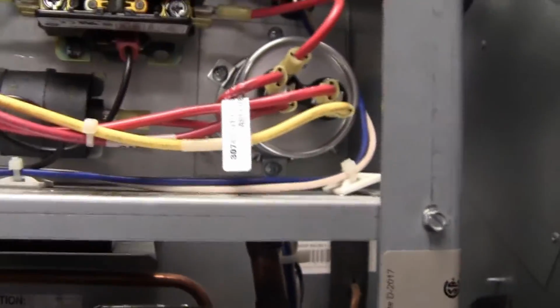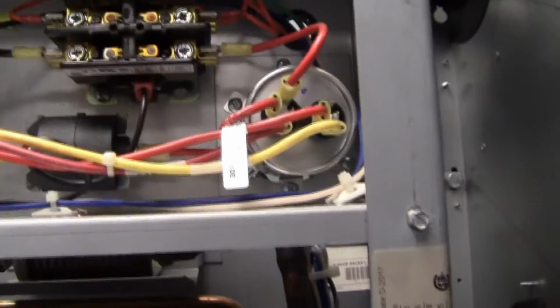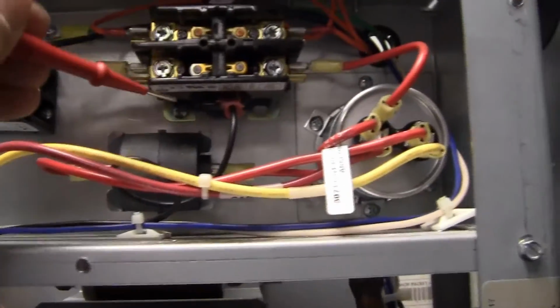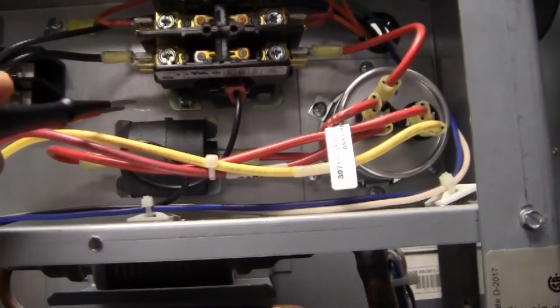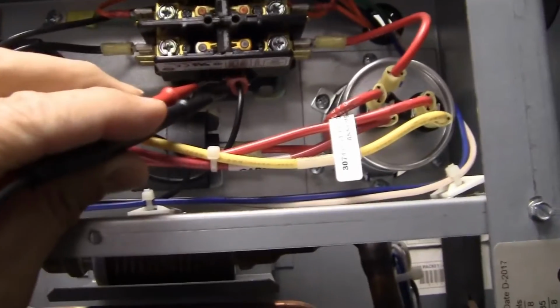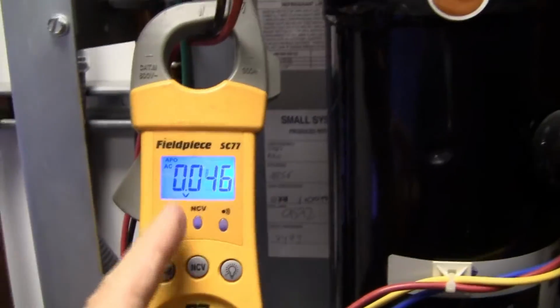So this thing has experienced some pretty good wear and tear. Anyways, I've already checked for voltage across the leads right there at the bottom. Hang on one second. Okay, so it's hard for me to do this and hold the camera at the same time, but basically, without holding the camera in my hand, I checked voltage from this lead to this lead right up here, which is the contactor coil, and it came out with 0 on my Fieldpiece. Now, that means there's no coil voltage, but the compressor is stuck in.